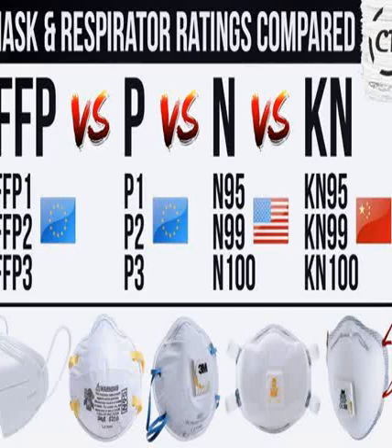EN 149 tests the ability of masks to protect the wearer against inhaling liquid and dry aerosols. It makes no statement about, and does not specifically test, the suitability of such masks for infection control against airborne transmission of pathogens through respiratory droplets. Nevertheless, FFP2 and FFP3 masks are commonly used for this purpose in medical practice.